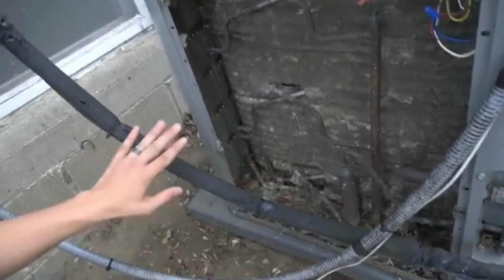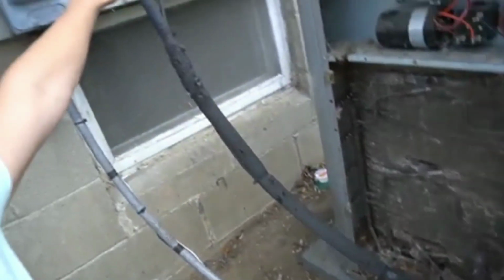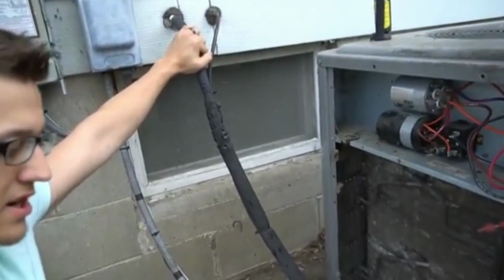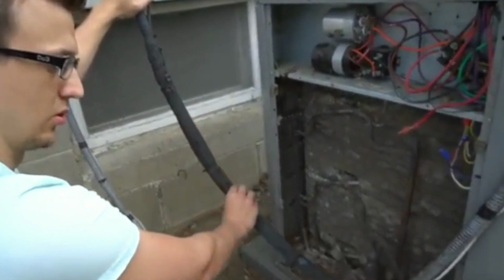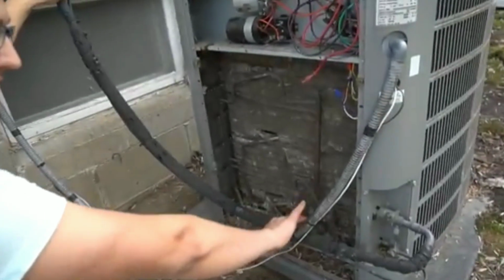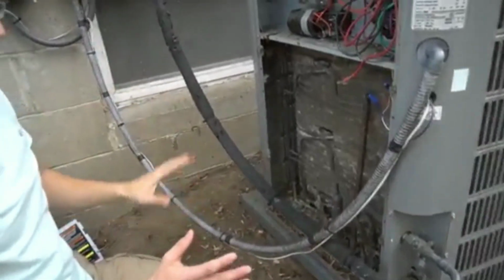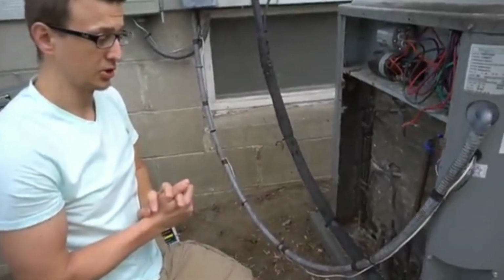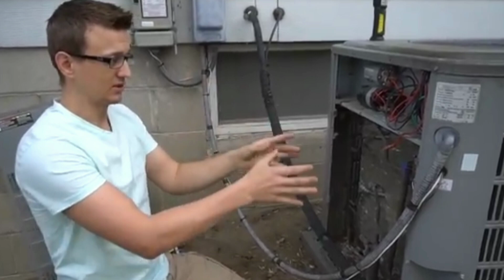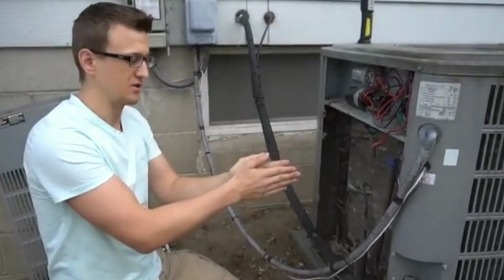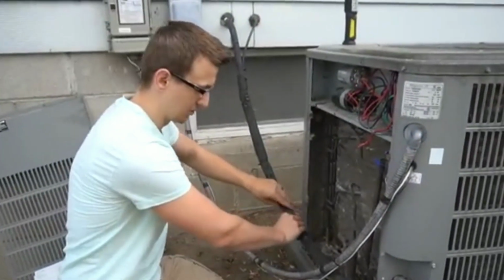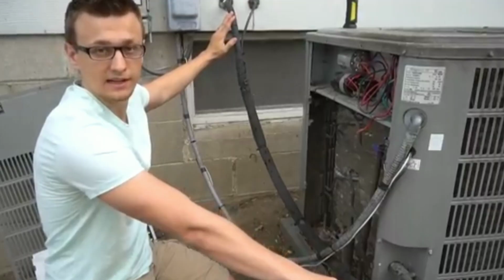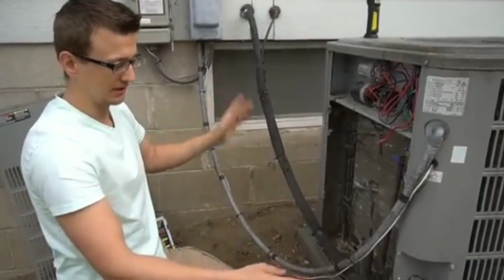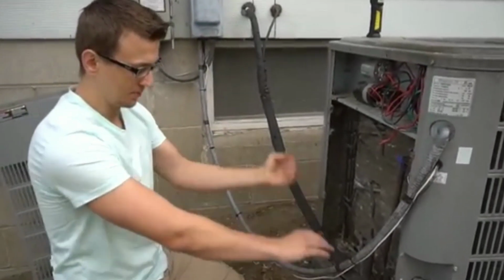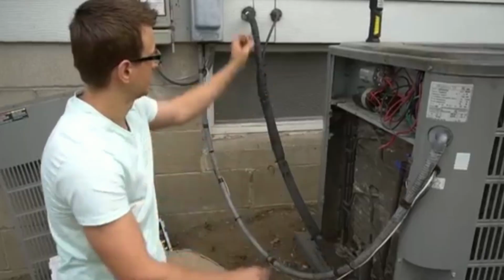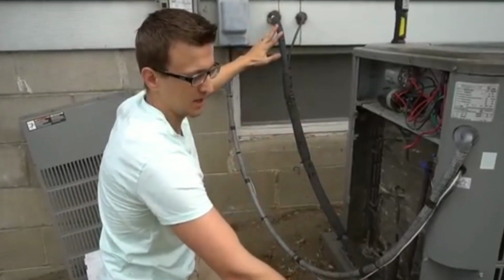disappears. The insulation is there so that the refrigerant or the Freon does not turn into a liquid too fast. And I know I might be getting a little bit technical, but basically, long story short, to extend the life of your compressor on your AC unit, they put this insulation on this thick line. So if your insulation is completely gone, I would get another piece of this foam insulation and put it over this thick pipe right here.